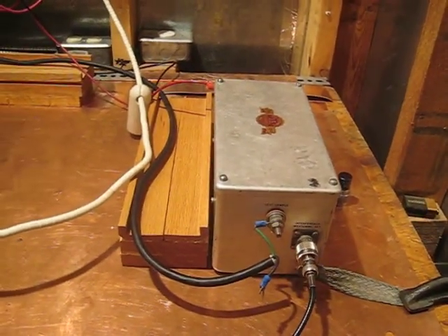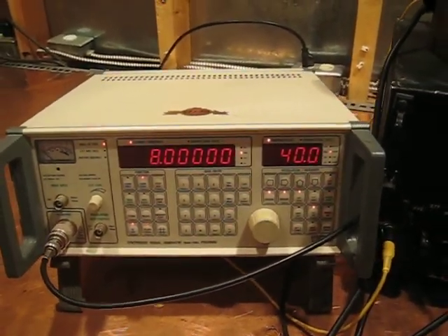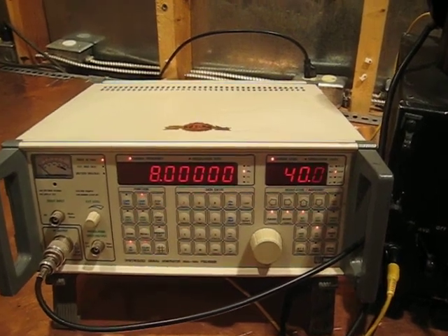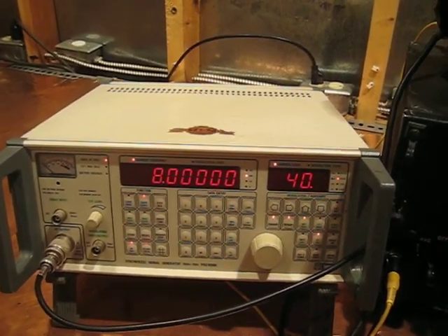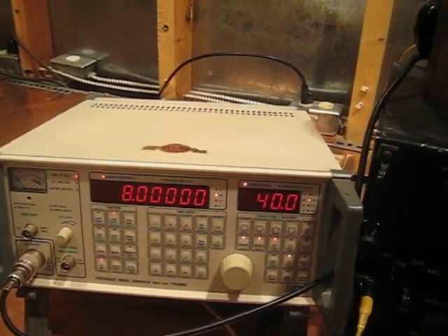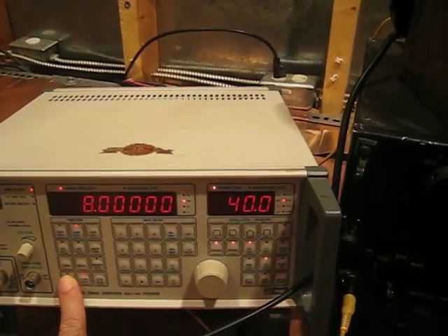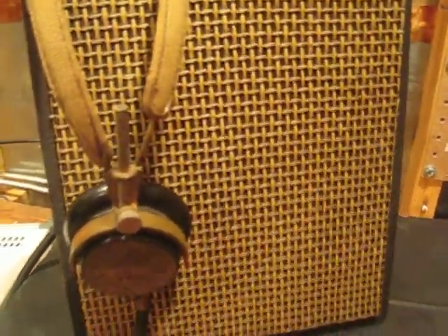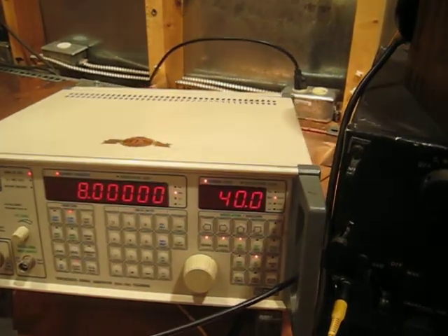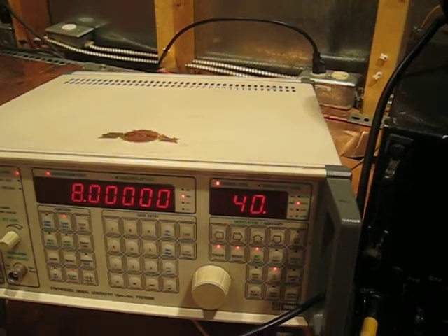Now, it's time here. We're going to go ahead and turn the RF on out of the signal generator. It should be noted that the signal generator has 1 kilohertz modulation at 90% imposed on the 8 megahertz carrier. It is the 1 kilohertz modulation that we will be listening for when we apply the RF signal. Okay.